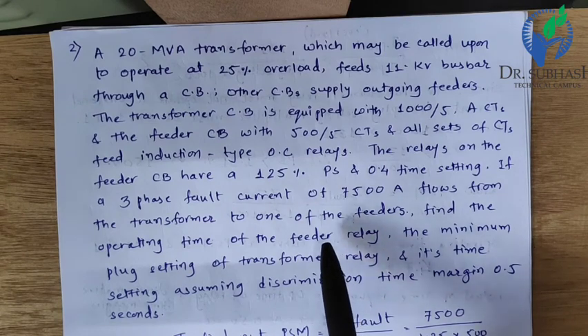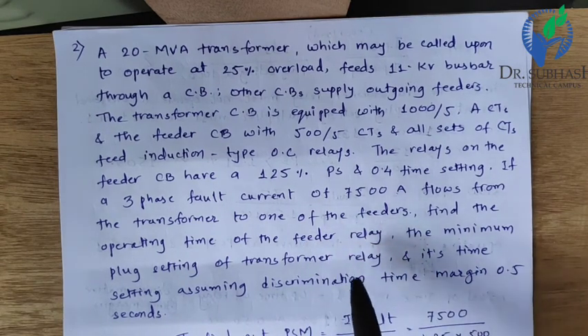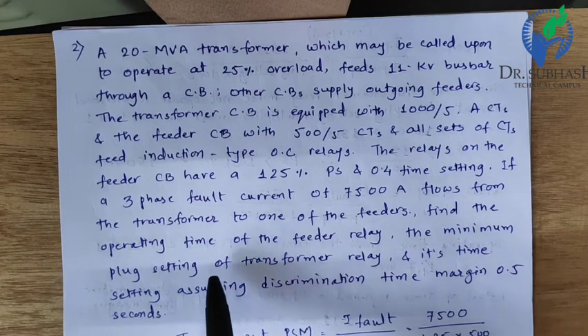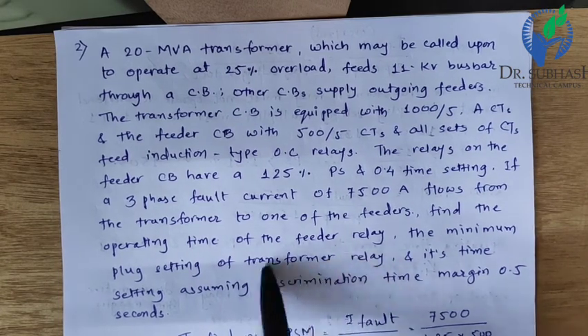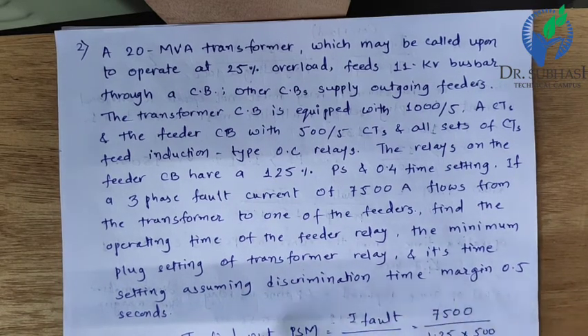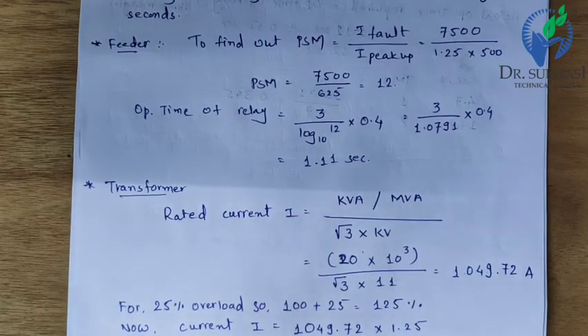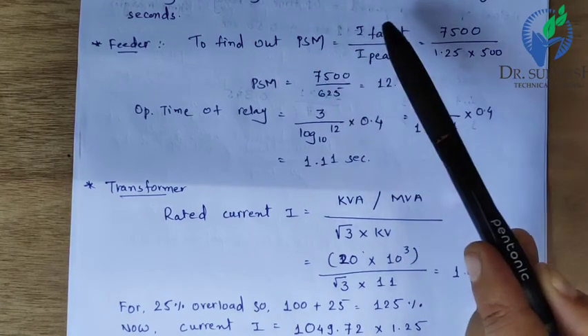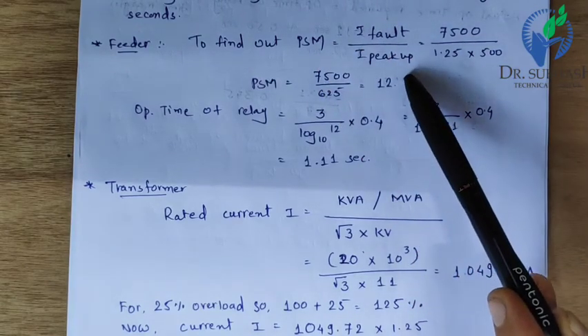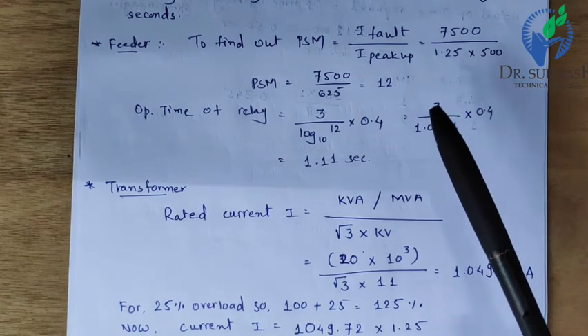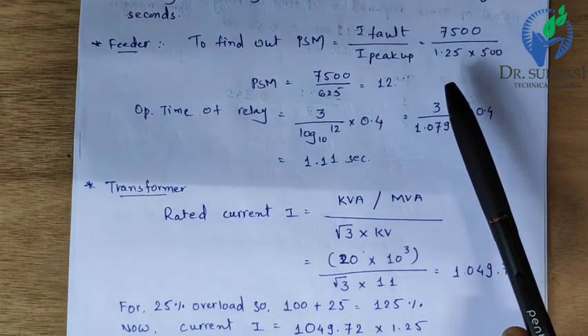We must find the operating time of the feeder relay first, then the minimum plug setting of the transformer relay and its time setting, assuming a discrimination time margin of 0.5 seconds. For the feeder, PSM equals fault current divided by pickup current. The feeder relay has 125% plug setting applied to a 500 A primary current.